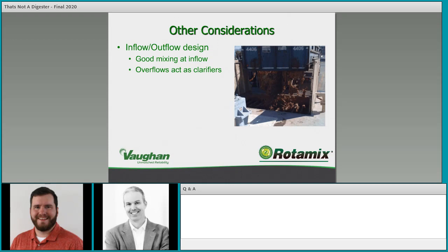You can keep heavier solids off the bottom with good mixing, but they won't exit the system via an overflow — eventually they'll collect and overwhelm the system. If you have an overflow design, you can look at changing to a withdrawal point, or adding a withdrawal point and alternating between the two. A withdrawal point near the bottom and in the center is recommended. Even with a shallow cone or flat floor, things tend to migrate toward the middle, making that your best withdrawal point to keep things moving through your facility.